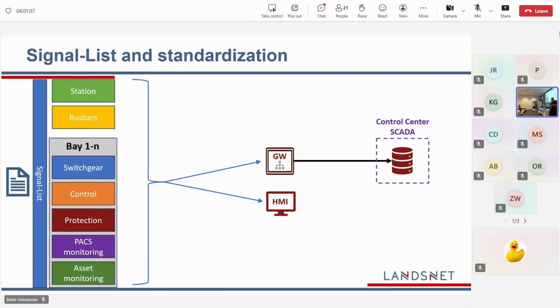Again, into a signal list and standardization. This is a very high-level view of the signal list. We have some station signals, bus bar, then different things for each bay, and we used to send all these signals to the gateway HMI. That also included asset monitoring signals, like the SF6 or the gas monitoring of the GIS, and lots of signals going this way.